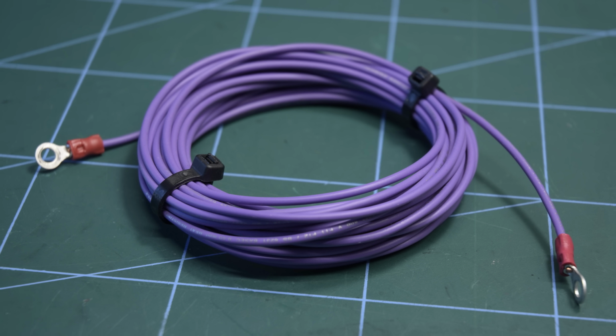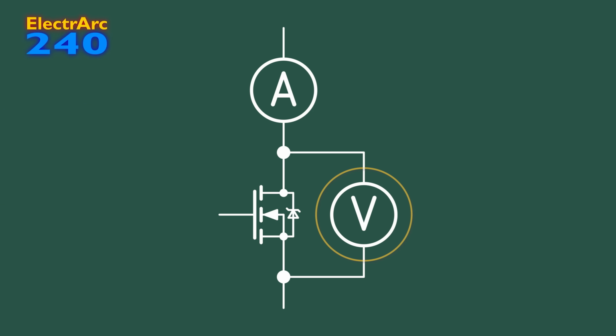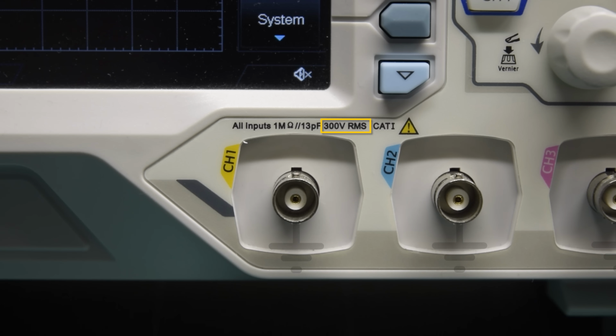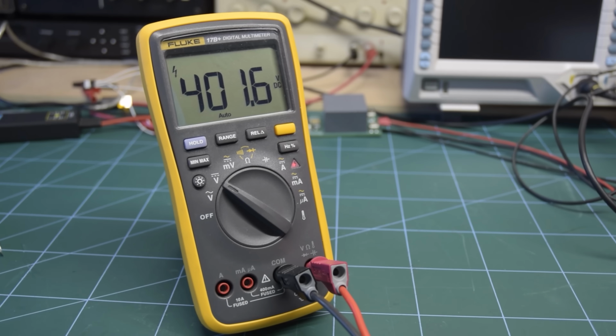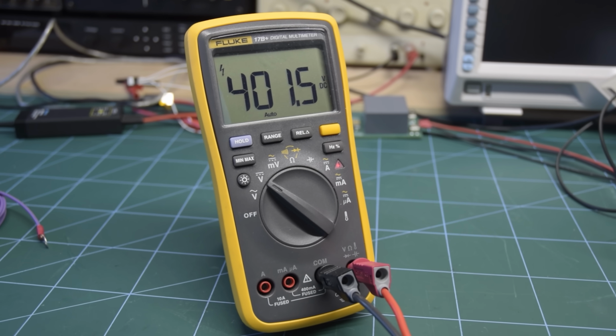Next, we need to set up our measurement of voltage and current. Voltage is fairly easy, as long as you remember to consider the rating of your probe and any ground loops if it's not isolated. As I'm running at voltages in excess of 400 volts, I'm going to be using a high voltage differential probe.